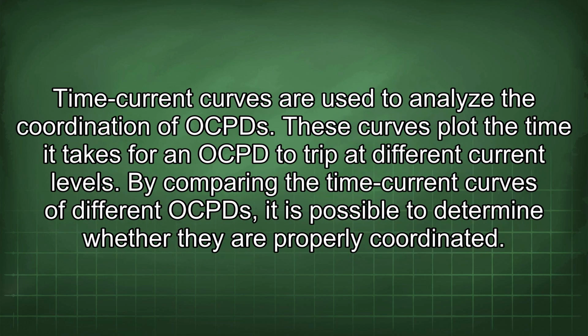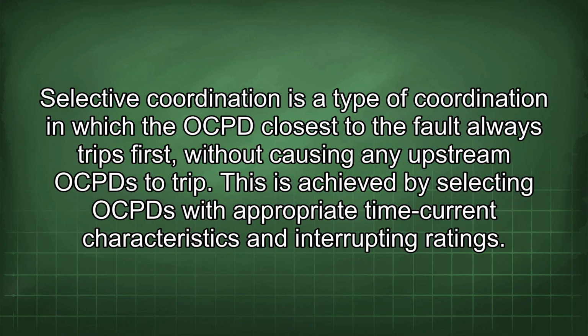Time current curves are used to analyze the coordination of OCPDs. These curves plot the time it takes for an OCPD to trip at different current levels. By comparing the time current curves of different OCPDs, it is possible to determine whether they are properly coordinated. Selective coordination is a type of coordination in which the OCPD closest to the fault always trips first, without causing any upstream OCPDs to trip. This is achieved by selecting OCPDs with appropriate time current characteristics and interrupting ratings.